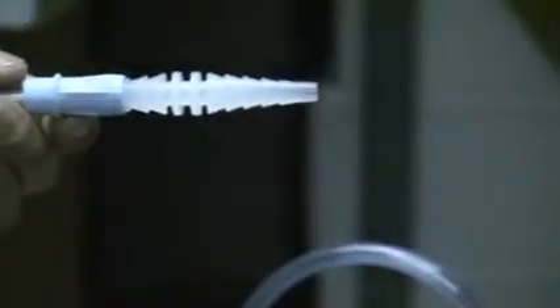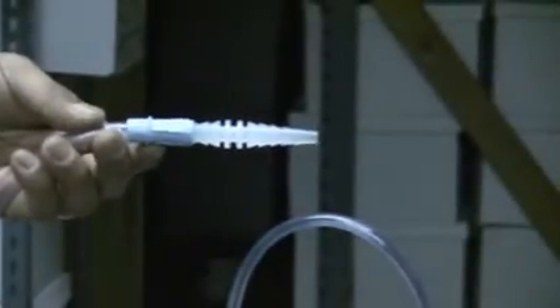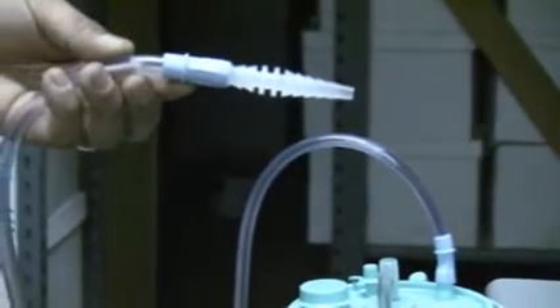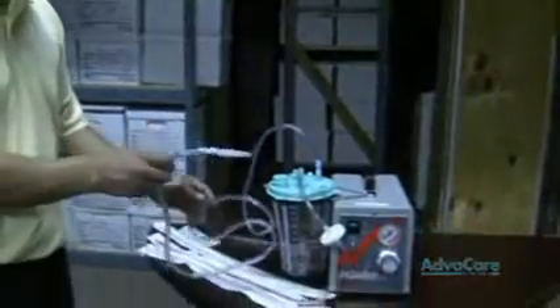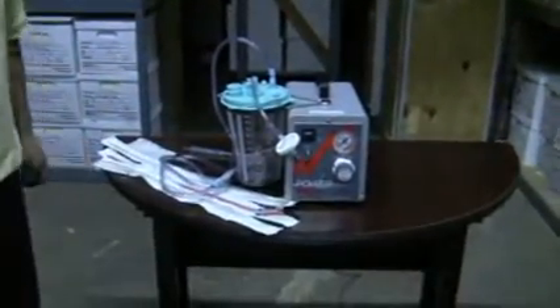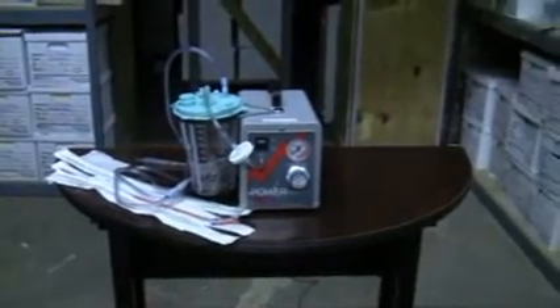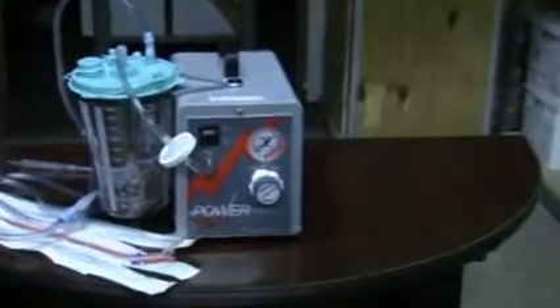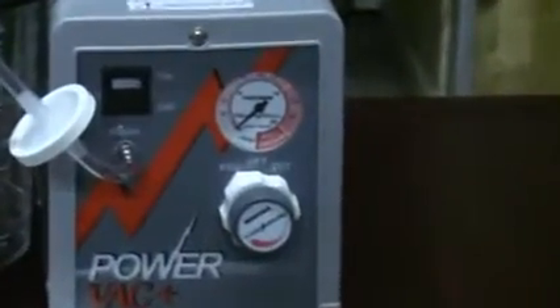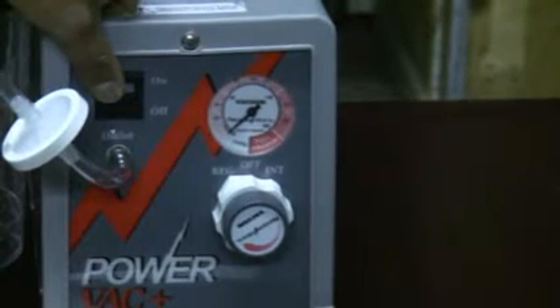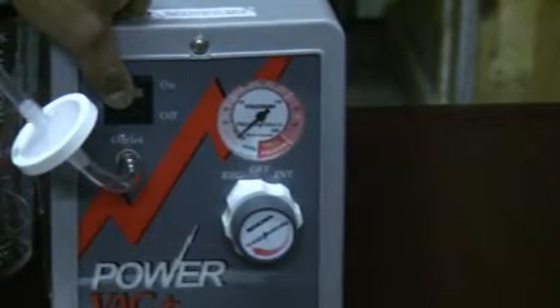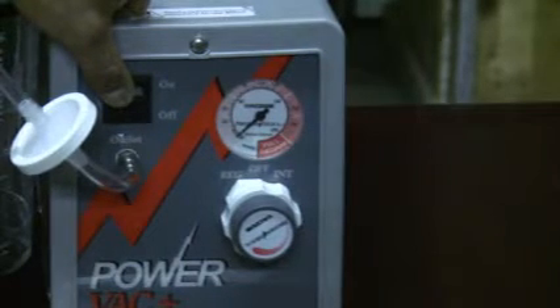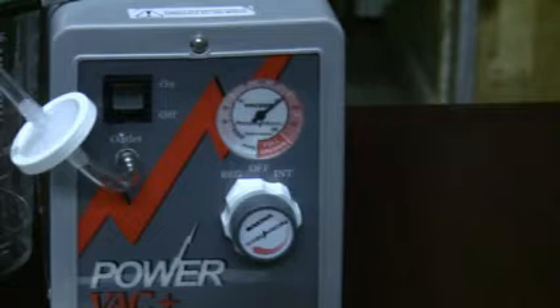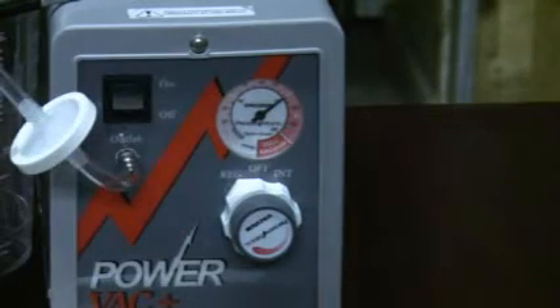The other end of your 5-in-1 connector is the side that should connect to your patient's NG tube or G tube for your intermittent suction. Intermittent suctioning is usually used for gastric suctioning, and we said does have an intermittent time cycle of 16 seconds on with 8 seconds off. So we will power on our intermittent suction machine again to get power. It was initially left in the regular position, so when we power on, we will see our vacuum needle go up on our pressure gauge.